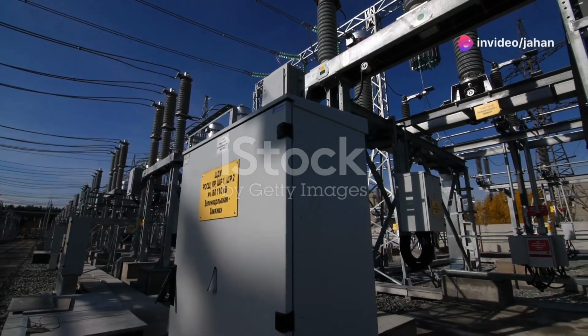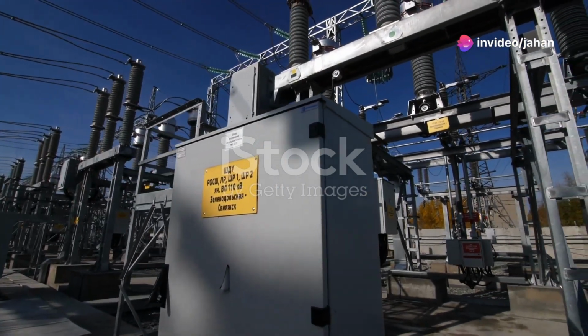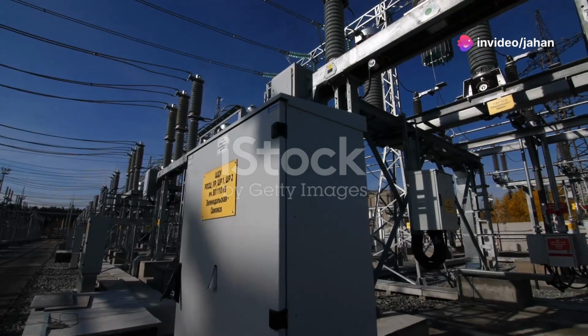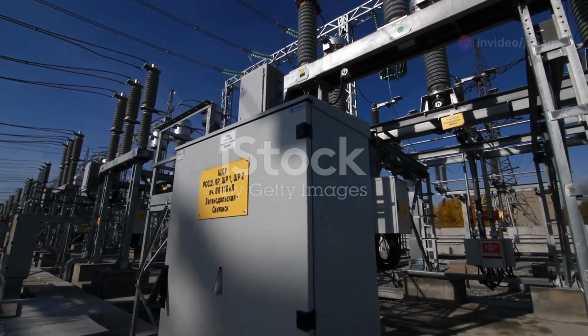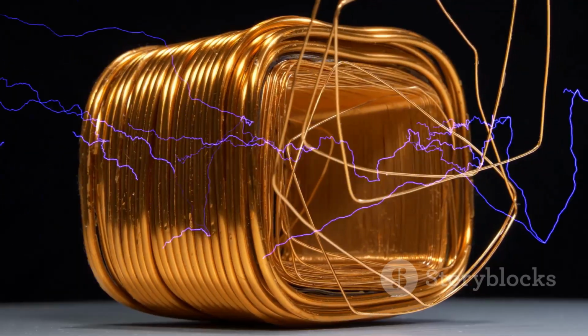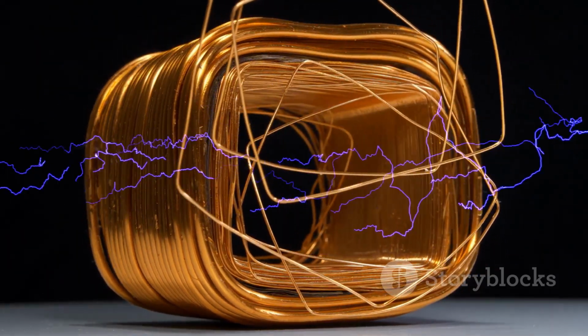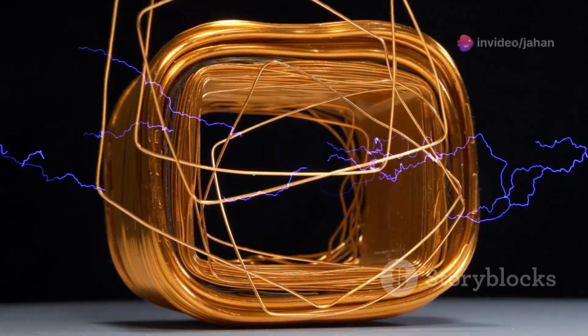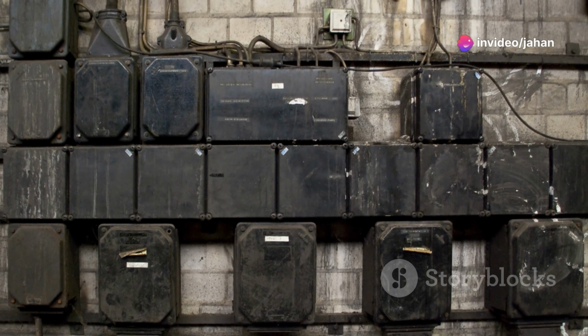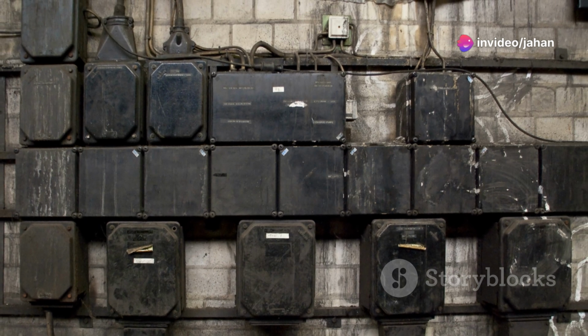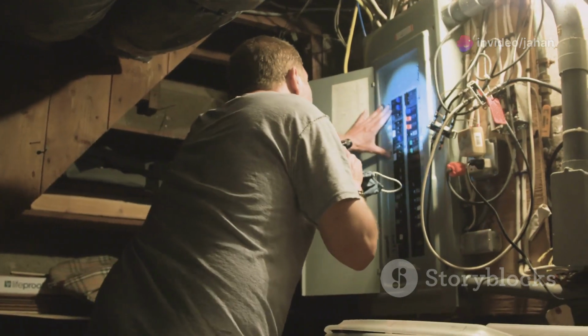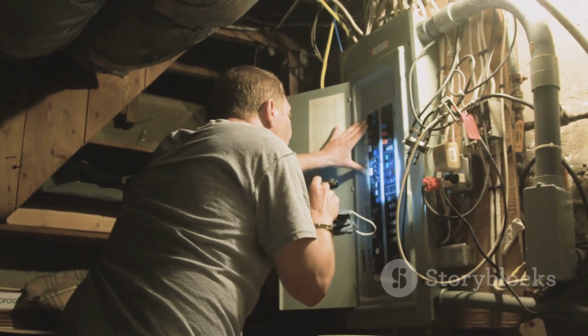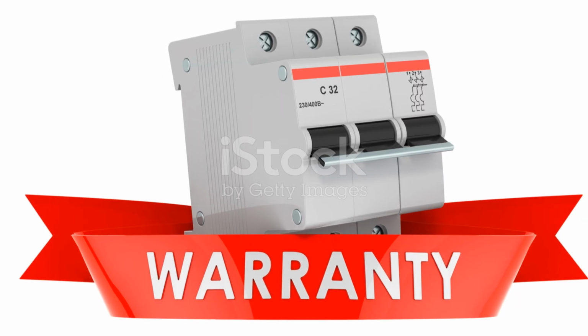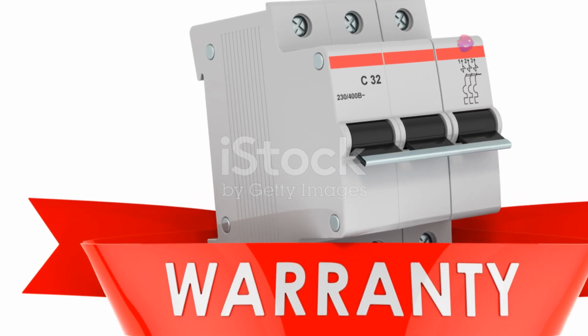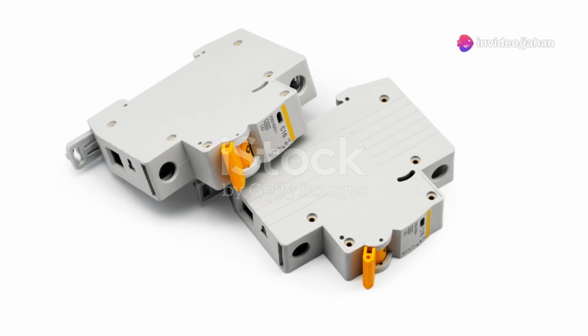They do this using a special chamber called an arc chute located within the breaker itself. When an ACB interrupts a high current flow, an arc is inevitably formed. However, the arc chute forces this arc to travel upwards through a series of metal plates. These plates act like a maze, cooling and stretching the arc as it travels, rapidly cooling it and causing it to extinguish or quench effectively. So not only do ACBs interrupt dangerous currents, but they also have a built-in firefighting mechanism. How cool is that?